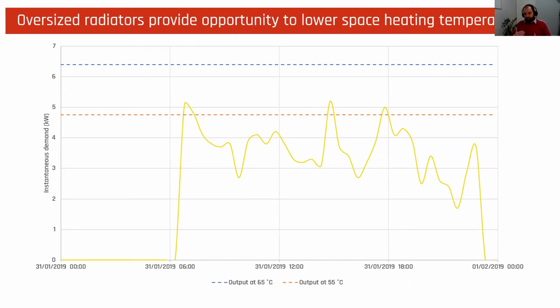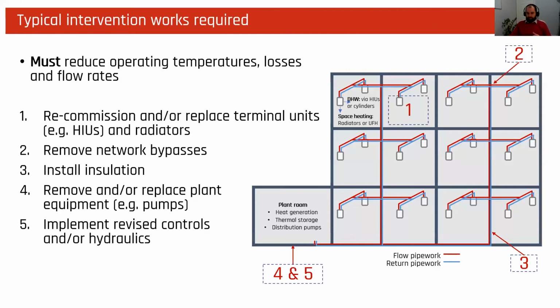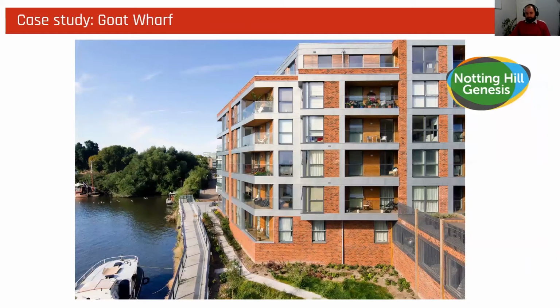And you could actually drop the whole temperature of the system down by 10 degrees and there'd still be comfortable headroom. So that's already shown that we've got an opportunity to drop the temperatures of the system without having to replace a lot of equipment within people's dwellings. And I'll quickly go through this slide, but again, similar to the HNOO project, these were the kind of issues we found. So, recommissioning, network bypasses, insulation, replacing plant equipment, and implementing better controls of the plant room.